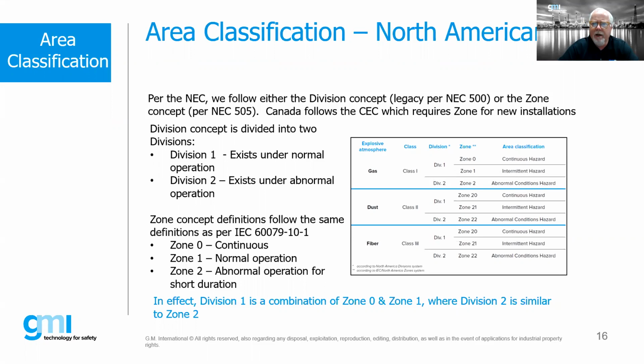Division 1 is an area in which a flammable gas exists under normal operation. Division 2 exists under abnormal operations. So in generalities, if we look at Division 1 versus zones, Division 1 encompasses both a Zone 0 and a Zone 1 type environment in the international community. Division 2 is roughly the equivalent of Zone 2.